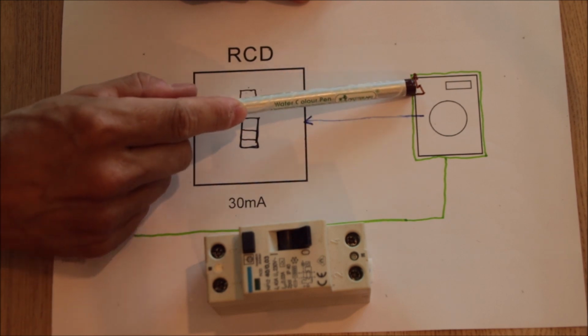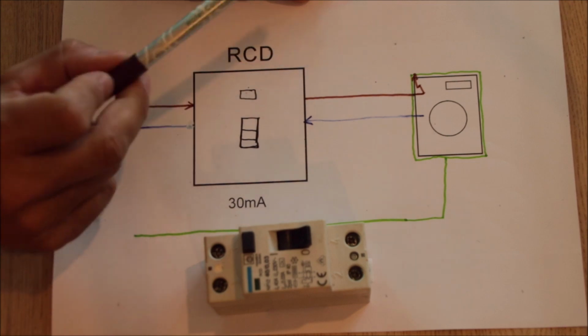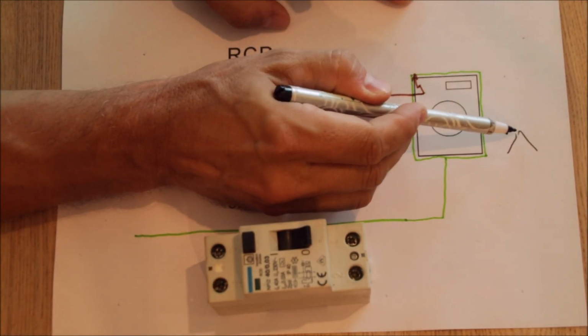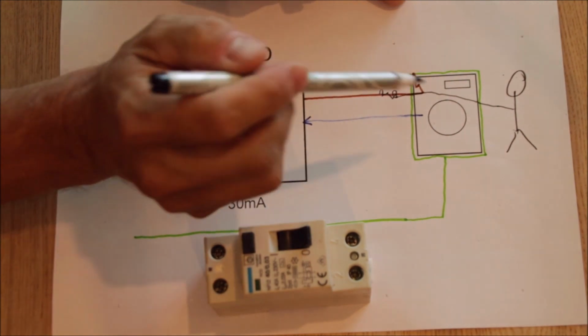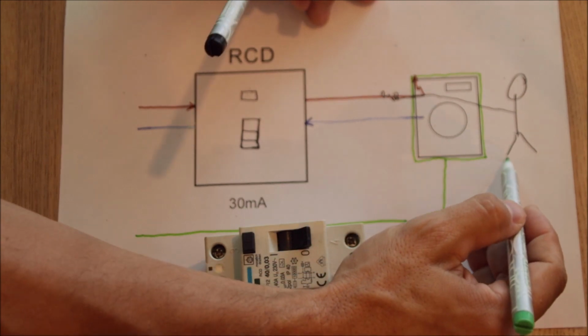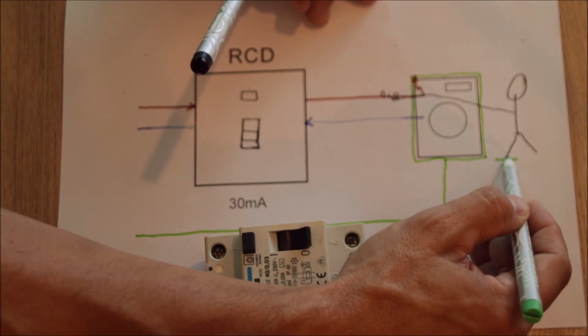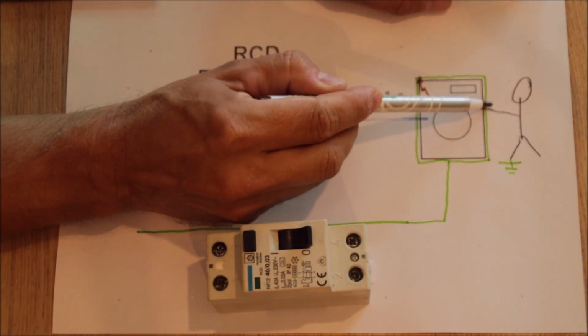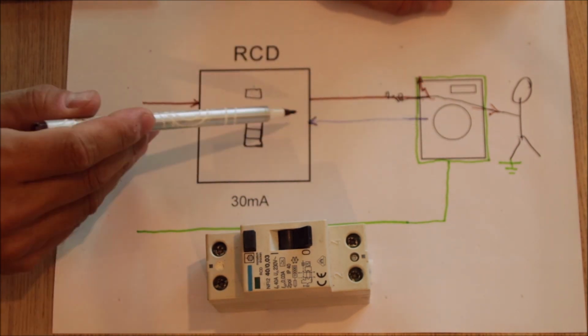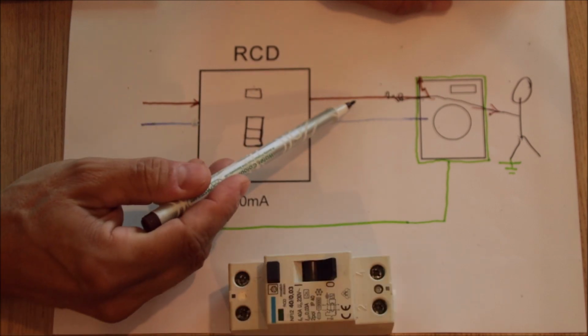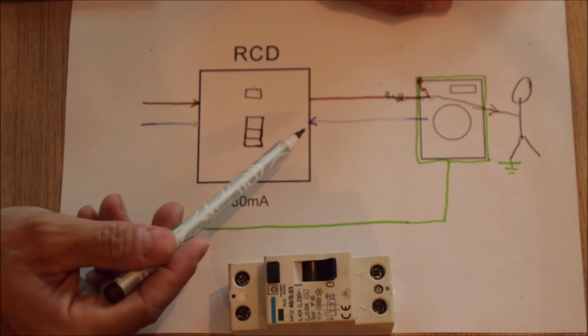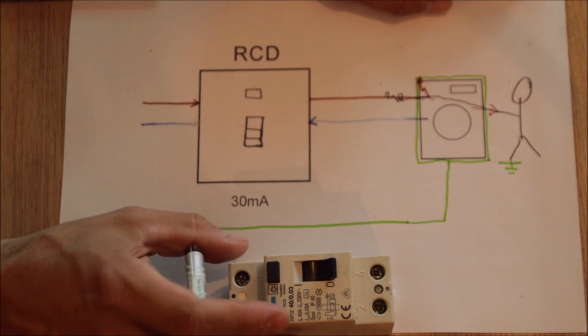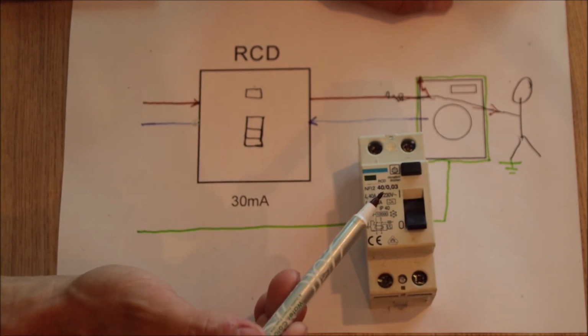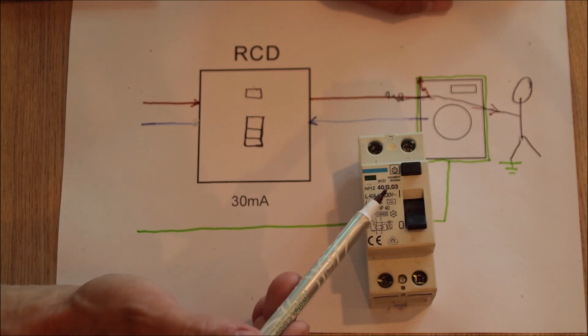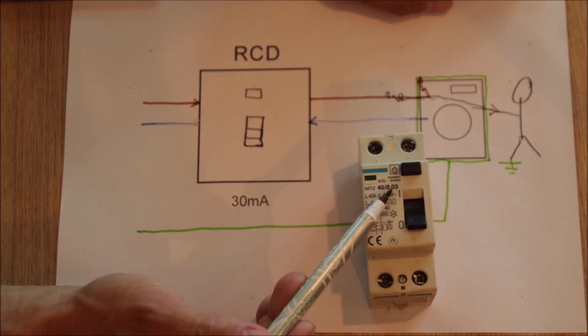But let's say that is just a leakage. So low current leakage, or because maybe our human is somehow coming in contact here with our hot wire, and because the human also stands on earth, there will be current flowing now over the human and bypassing the neutral return flow. The input current will be different than the output current. So output current will be less than the input current, and RCDs as this one here.